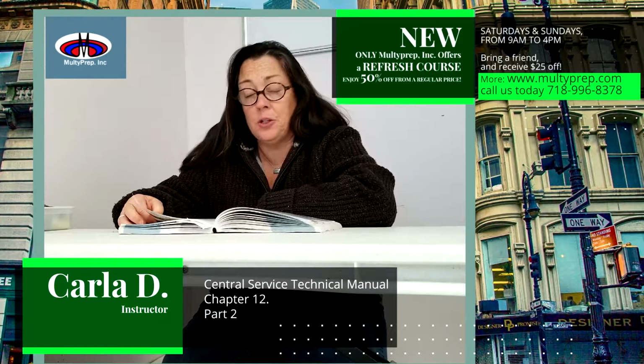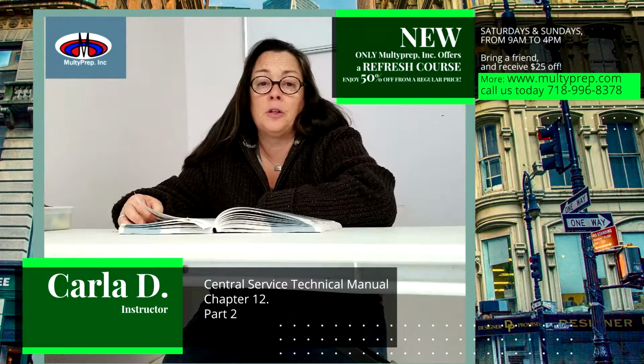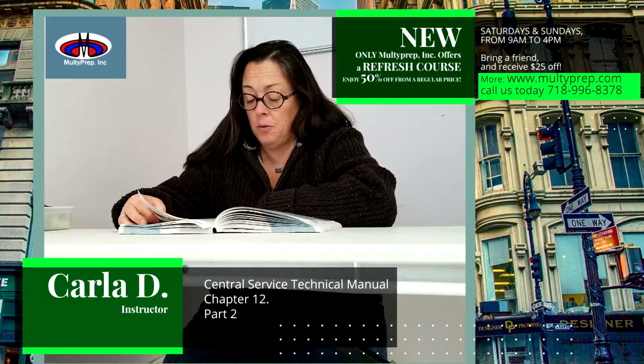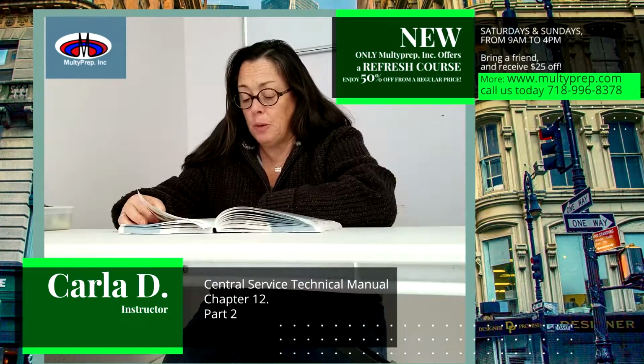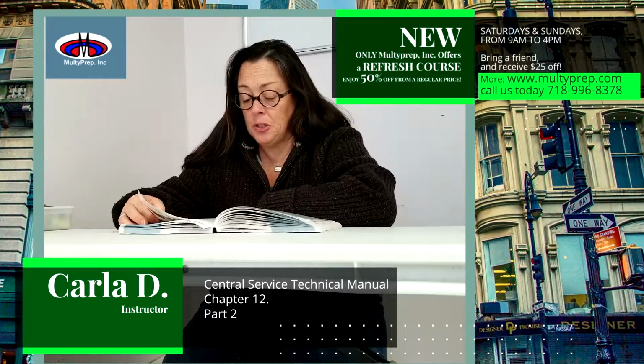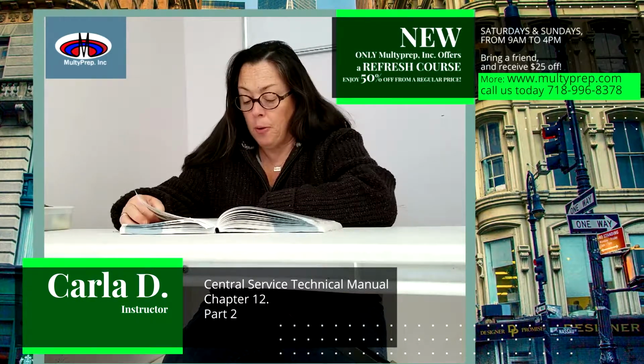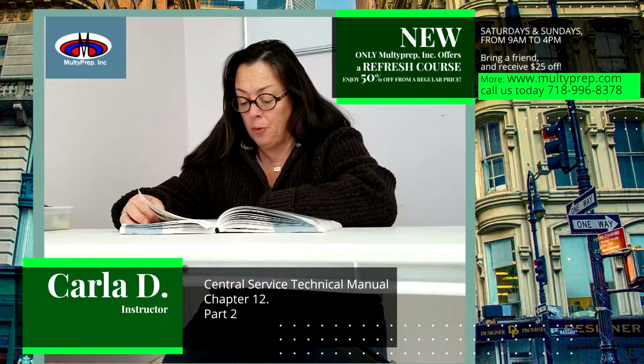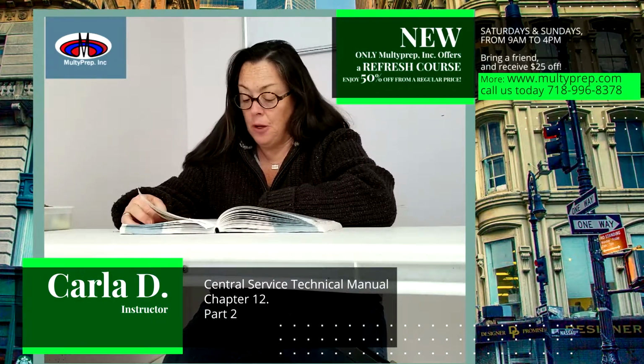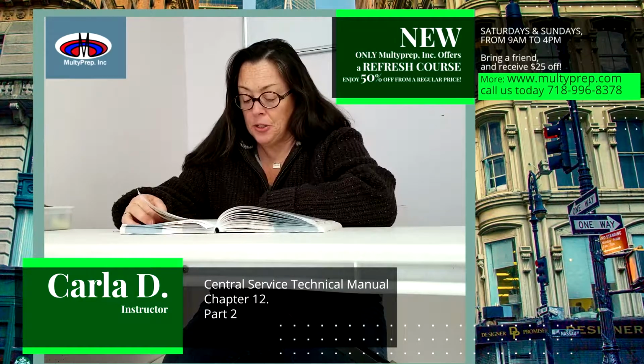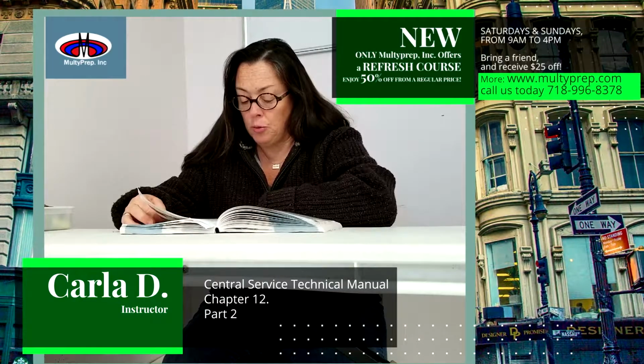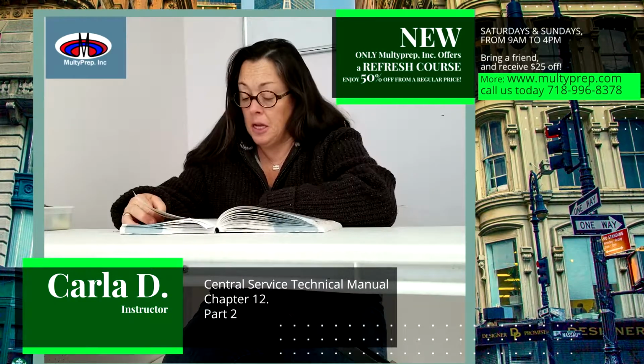The continued use of broken or excessively worn instruments could put patients and/or facility personnel at risk. See Figure 12.7 for an example. Check multi-part instruments. Instruments that have been disassembled for cleaning should be reassembled and tested for proper function, and then disassembled again for sterilization. See Figure 12.8. Note: small parts such as wing nuts should be placed in an approved containment device. See Figure 12.9. When placing disassembled instruments inside the tray, keep all parts close to one another so they can be readily accessible in the operating room.